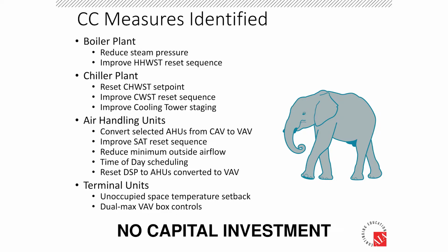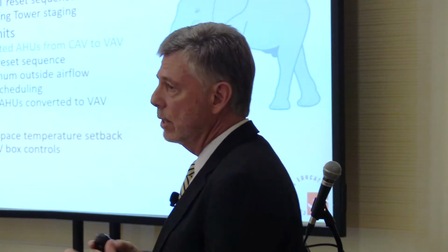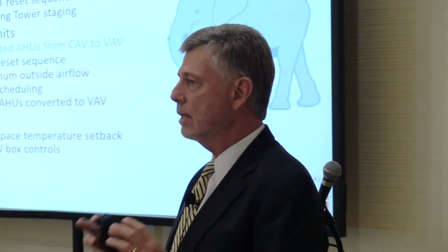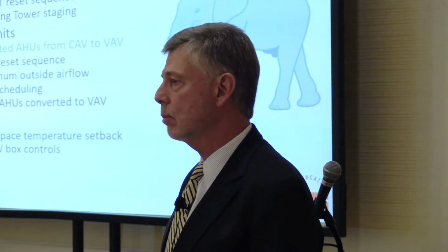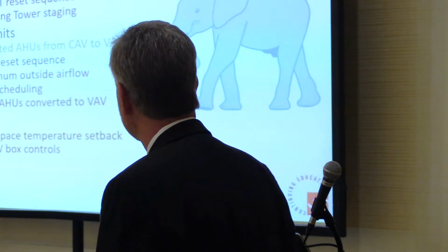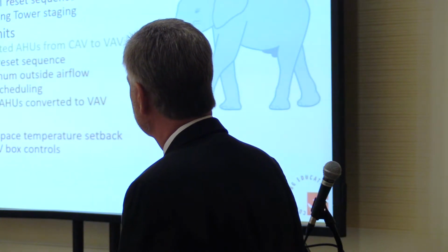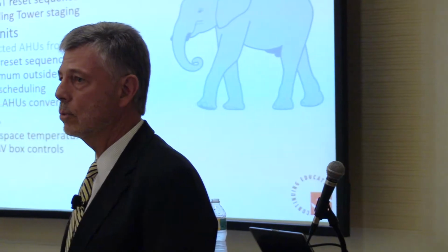We identified a number of measures in addition to the conversion of the variable air volume boxes or the constant volume boxes. That was obviously the elephant in the room and the largest contributor to the savings. This is one reason we just didn't want to isolate on just that one measure, because we knew in this hospital there were likely to be other things that would be applicable to saving energy and improving the environment in that hospital. Now, I won't read a lot of these to you, but common things I'm sure you've seen in your own work as well.